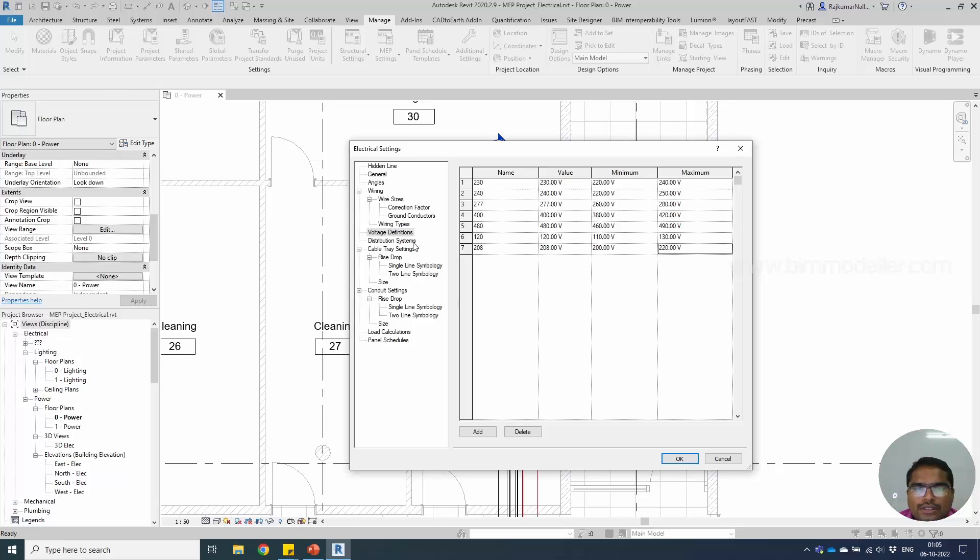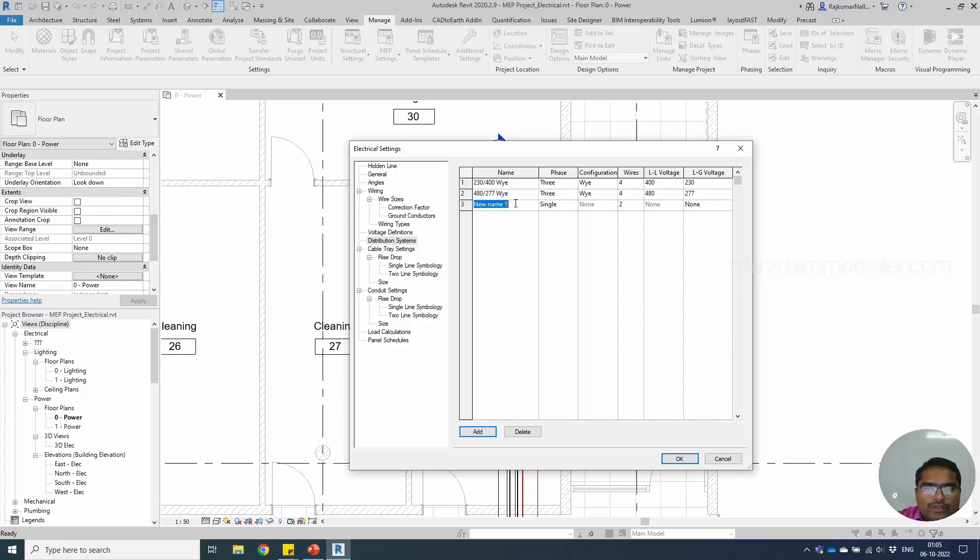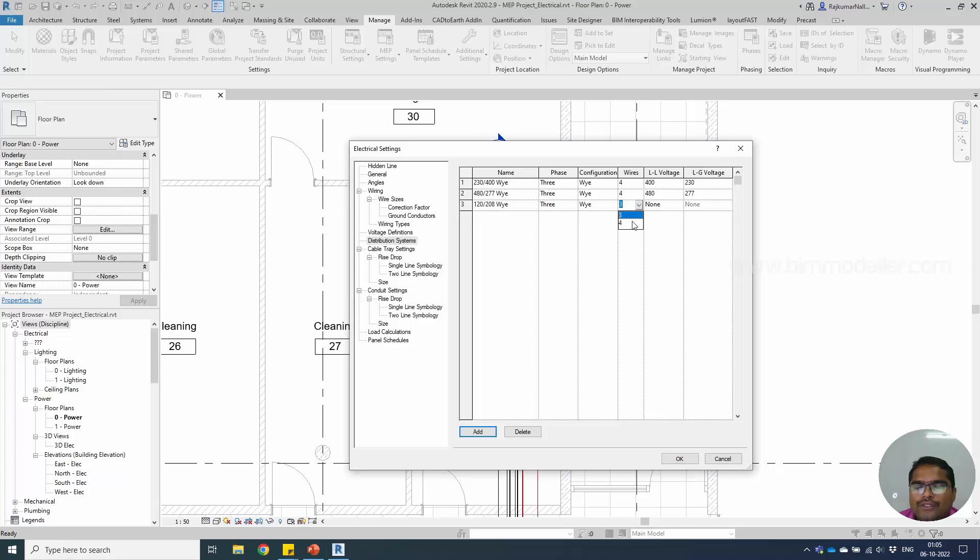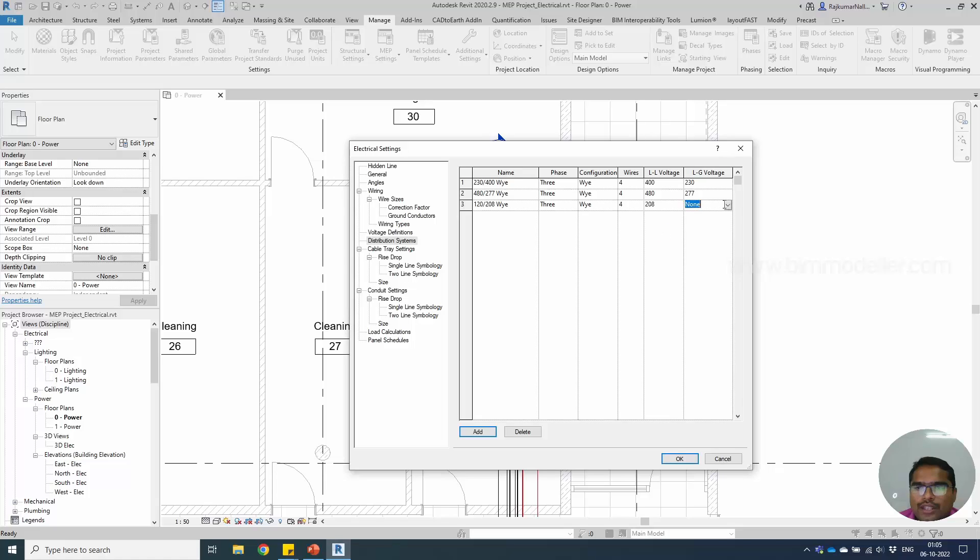Once the voltage is defined, you will be able to create a new distribution system, say 120 or 120 divided by, just a name that defines what it is. It's going to be three phase and it's going to be Y connections, will have three phase three lines and four wires for the neutral. The line to line voltage will be 208. The line to ground value will be 120.